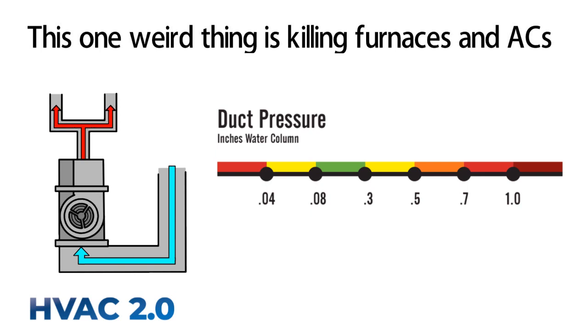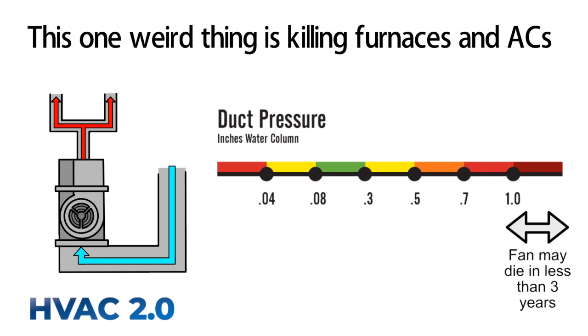The mandated motors are far more sensitive to duct pressure than the old type. If the duct pressure inside your system is just right, it will be quiet and use very little energy compared to the old motor. If duct pressure is too high, your new, more sensitive fan motor may be overworked and die in less than 3 years, which can cause an expensive repair.